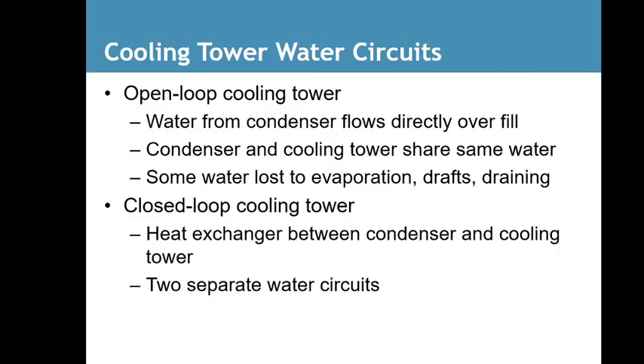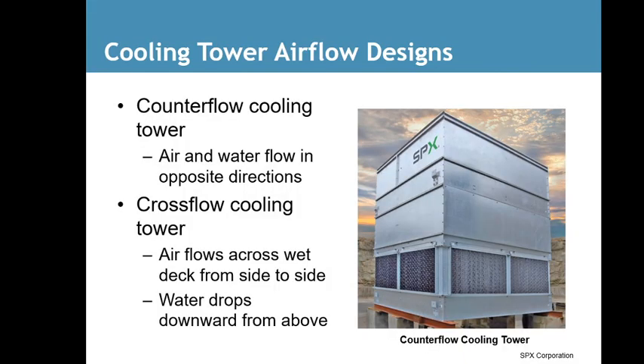Cooling tower water circuits: open loop cooling tower. Water from the condenser flows directly over fill. Condenser and cooling tower share the same water. Some water is lost to evaporation, drift, and draining. Closed loop cooling tower: heat exchanger between the condenser and the cooling tower, two separate water circuits in a closed loop system. Cooling tower airflow design: counterflow cooling tower, air and water flow in opposite directions. Crossflow cooling tower, air flows across the wet deck from side to side, water drops down from above.